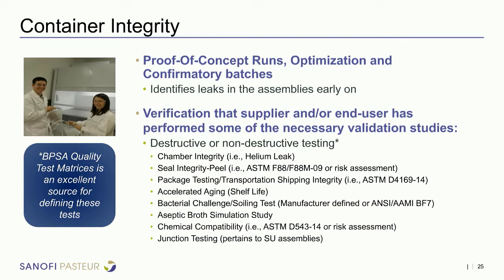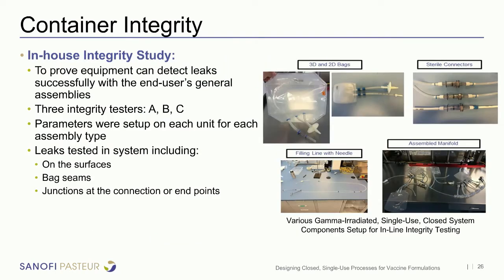I should note that the BPSA, the Bioprocess Systems Alliance quality testing matrices, is an excellent source for defining these tests. So our in-house container integrity study was done to prove that equipment can detect these leaks successfully with the end user's general assemblies. And when I say leaks, I mean gross leaks. So 3 integrity testers, A, B, and C, were tried, and they were the only ones on the market at the time. The parameters were set up for each unit and each assembly type. And that actually took some time to do, to set up all the pressures, time, and the general conditions to run the pressure changes.